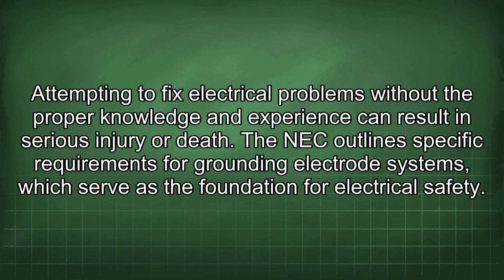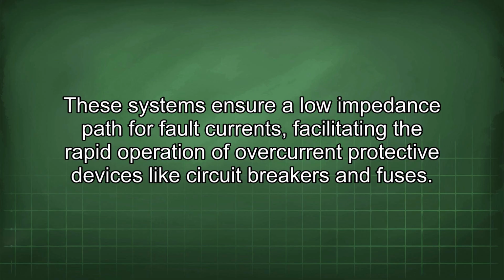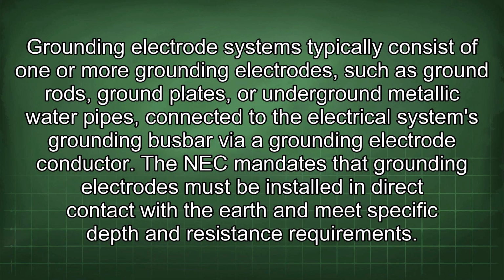The NEC outlines specific requirements for grounding electrode systems, which serve as the foundation for electrical safety. These systems ensure a low impedance path for fault currents, facilitating the rapid operation of overcurrent protective devices like circuit breakers and fuses. Grounding electrode systems typically consist of one or more grounding electrodes, such as ground rods, ground plates, or underground metallic water pipes connected to the electrical system's grounding busbar via grounding electrode conductor. The NEC mandates that grounding electrodes must be installed in direct contact with the earth and meet specific depth and resistance requirements.